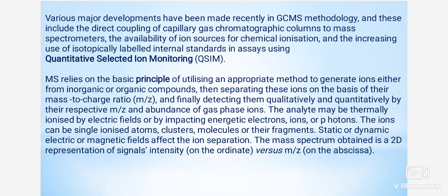MS relies on the basic principle of utilizing an appropriate method to generate ions either from inorganic or organic compounds, then separating these ions on the basis of their mass to charge ratio, M by Z, and finally detecting them qualitatively and quantitatively by their respective M by Z and abundance of gas phase ions. So the analyte may be thermally ionized by electric fields or by impacting energetic electrons, ions or photons.